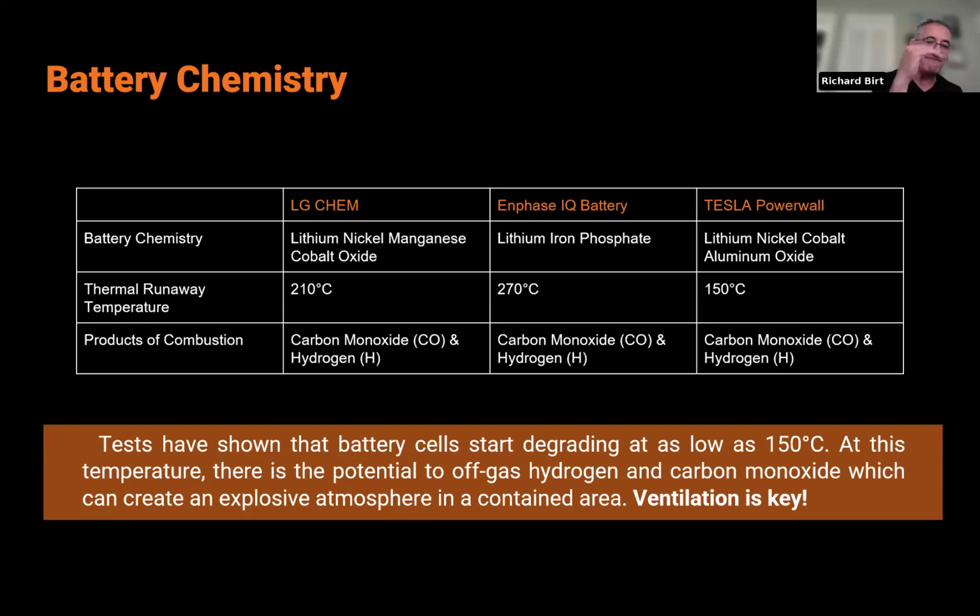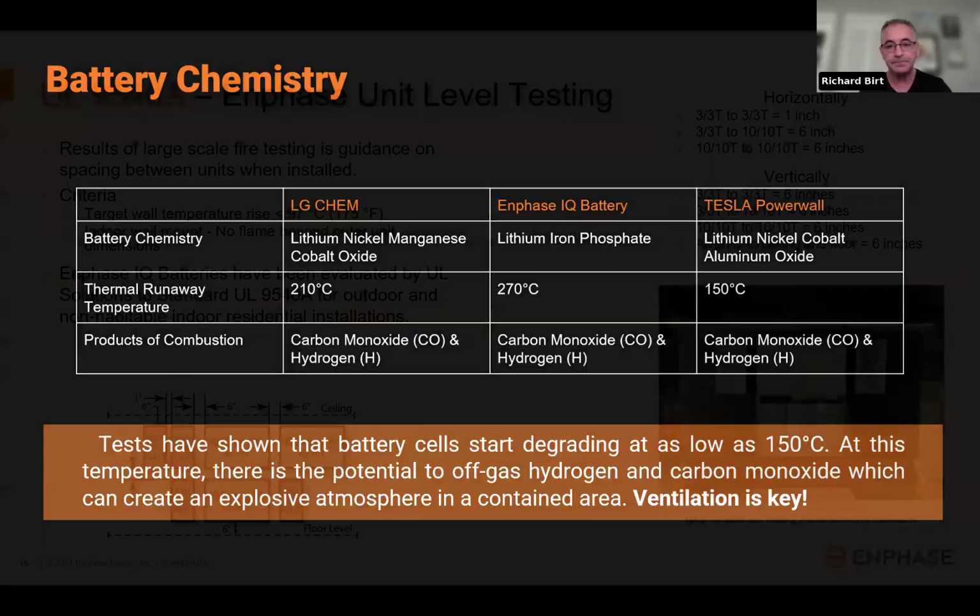And as I said, when it's vented, it's very, very safe where the hydrogen is being released, especially with LFP. Now, NMC and NCA, again, it's critical not to put water in there, for fundamental reasons: there are heavy metals in the smoke too. So at this point, sheltering in place is critical, understanding which way the plume's going if there is smoke, and letting it burn actively so it burns out the chemistry in those cells. So if we go to the next slide.